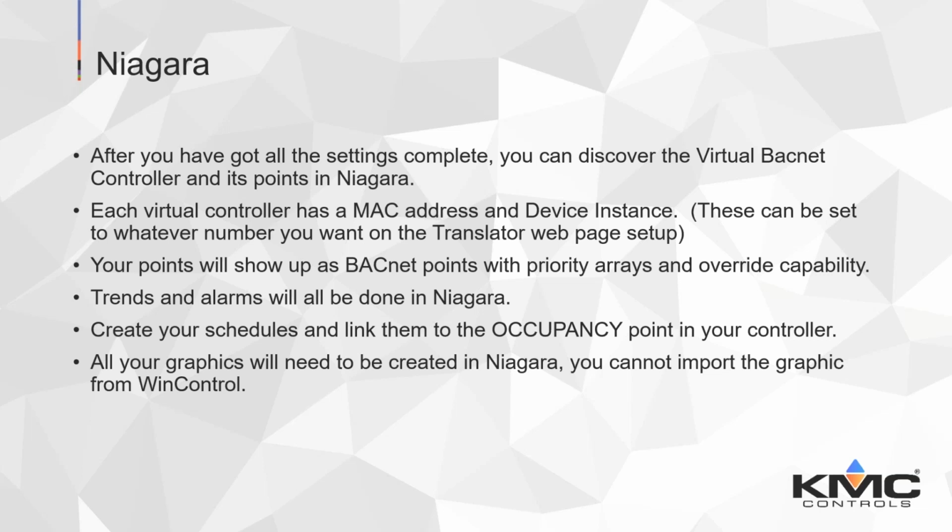Okay, and then the last question that came in is kind of a what-if question for a job site. We have multiple sites across a couple different states. Do I set one translator per site, and would those be BBMD'd all together, or how does it look if I have multiple sites? Yeah, you could definitely do the BBMD as long as they're on different subnets, and you would put the table in there for your BBMD to access all the sites. It kind of works like a router in that perspective.